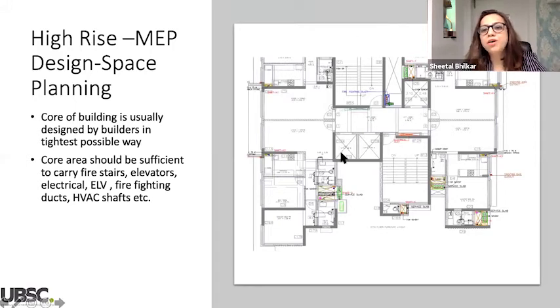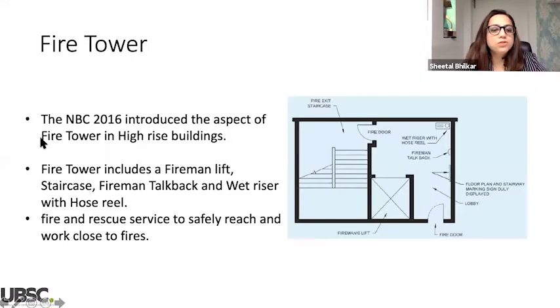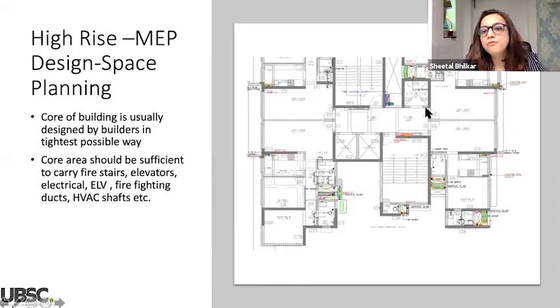So this is an example of a 39-story building where ducts are not provided, and we have to put ducts near these shafts. The core of a building is usually designed by architects in the tightest possible way. So as an MEP consultant, we should see to it that proper ducts are provided and that they are maintainable. At the beginning of the project, the MEP consultant should put their foot down, saying this much space is required. Otherwise it becomes very difficult to maintain later on.